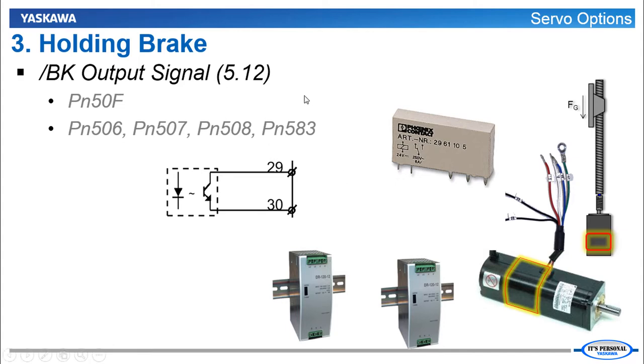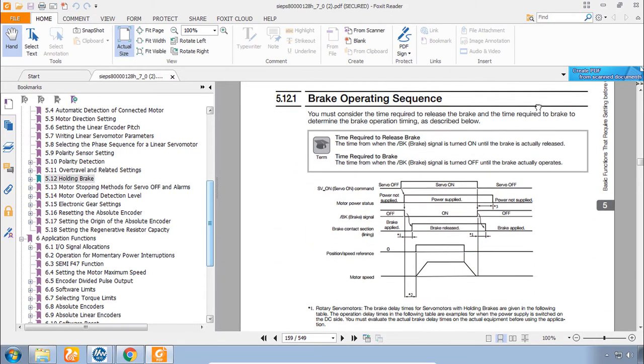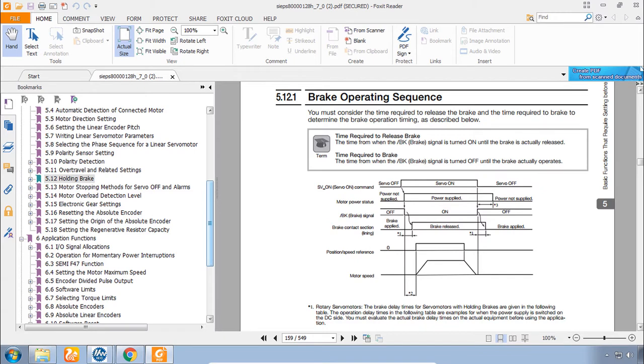The servo amplifier has an output labeled BK. Which can be wired to an external relay. This relay is then controlled by the output of the servo. And the output of the relay would be wired to the brake in order to apply power to the brake. Releasing the brake when the servo is on. So the output energizes. And the whole system releases the brake. And with the MPI-EC controllers this brake output is assigned to output number 1 on the amplifier's connector CN1. And the manual section 5.12 explains that also. And describes the different timing parameters. And parameters that control how the brake should be applied. If the motor stops during an alarm.